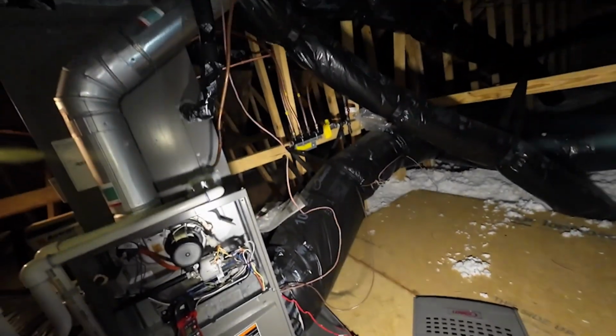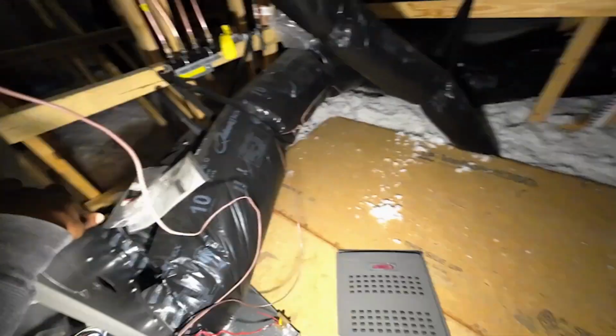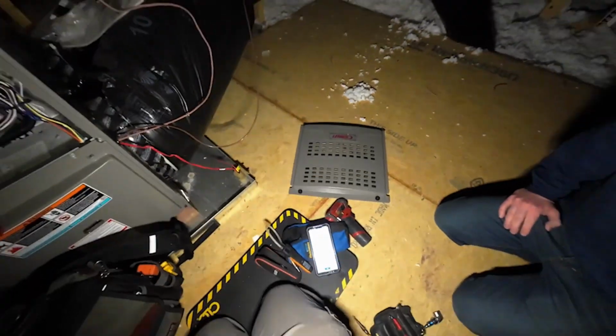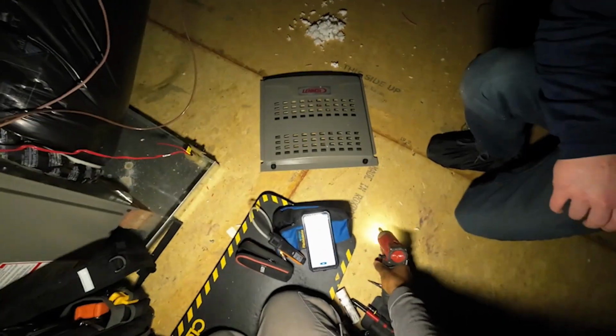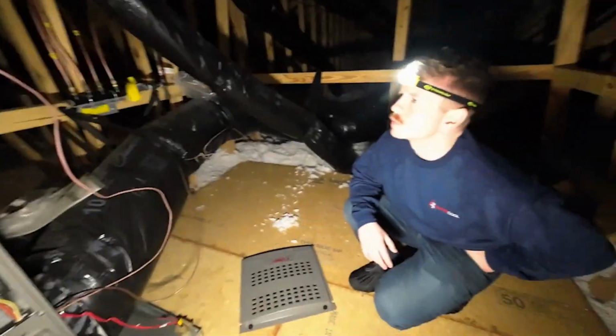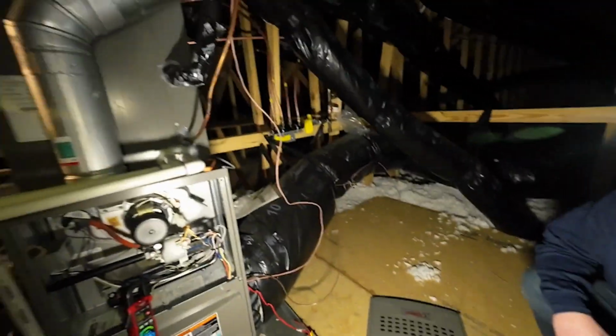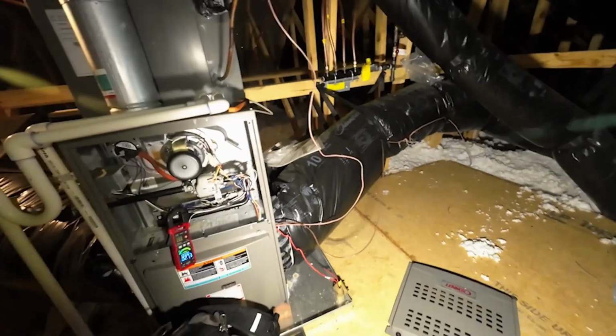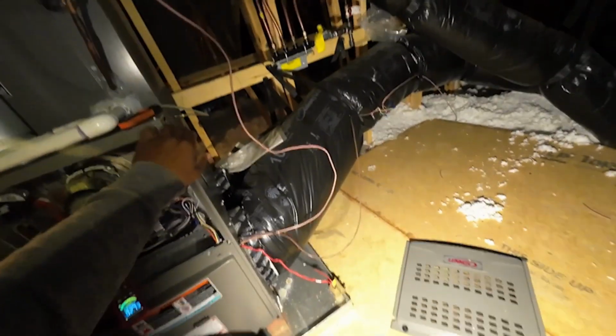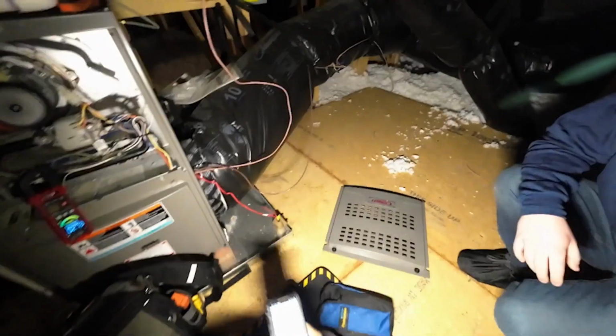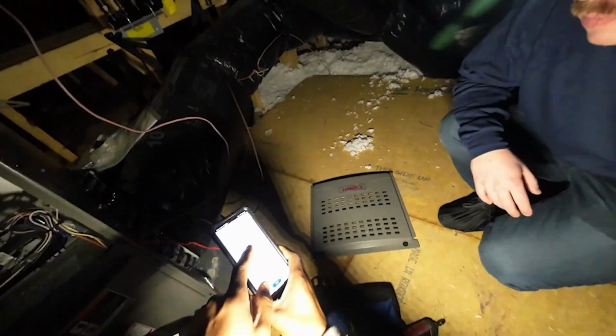So what I'm going to show you is this. We're going to hit right here. In order to get our total, I'm going to put a hole on the side of the furnace here, and I'll show you why here in a second. All right, so it's a quick tap right there. Now why I'm putting a hole here is because this coil is a resistance to airflow, right? There's going to be a coil in here that's got restrictive vanes and, you know, fins in there that's restricting air from getting up past it, okay? So that's going to be what they call a positive static pressure. This is negative. So look, there's our positive static pressure, 0.34 inches of water column.